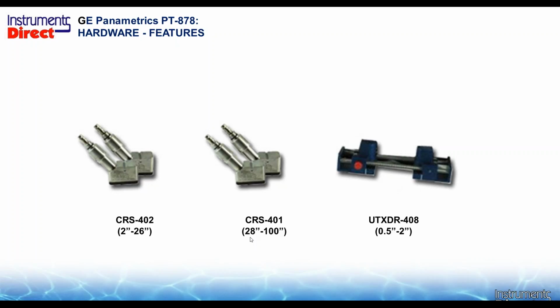Can it go smaller than 28 inches? Yeah, you can probably take it down to 10 or 8 inches, should you need to. In this case, this might be a better device for short runs of pipe with a heavier solid content, because it's a 0.5 megahertz. So stick with the pipe size first. Then for uniquenesses, to get off the manual, we can talk about some other things.